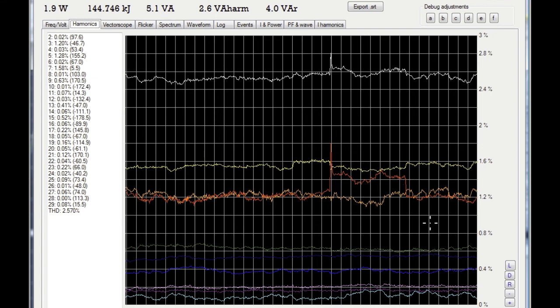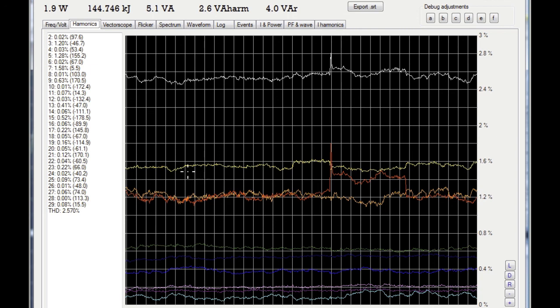Of course, any device that distorts the current waveform will distort the voltage waveform. So all these other distortions here, this 1.2% of third harmonic, this seventh harmonic, fifth harmonic, ninth harmonic, and so on, will all come from various appliances in the neighbourhood that are drawing distorted current waveforms. Things like motors, things like fluorescent light bulbs, electronic devices, and so on. They all contribute to give this net distortion.